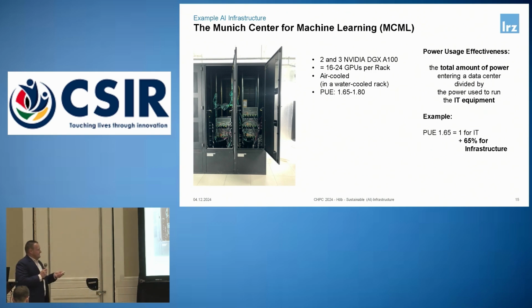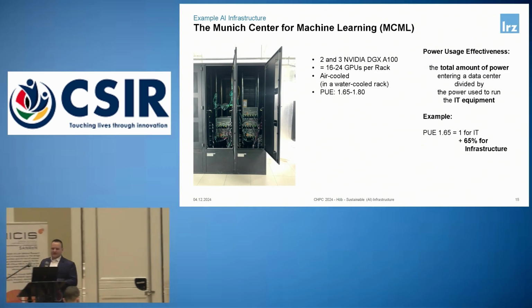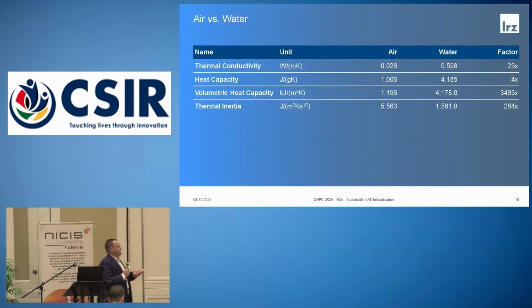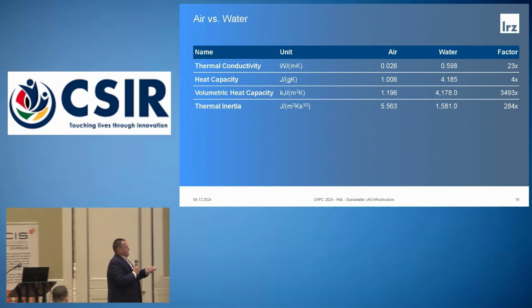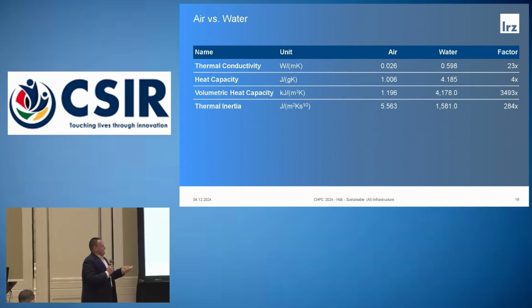Worse, this is the maximum amount we can put in such a rack, because the cooling capacity of this rack is 18 kilowatts, and each of them has 6 kilowatts, so there is a lot of empty space we cannot use for anything else, because all the cooling power is used by those 3 systems. We said, this is not good. We want to have another solution. And we know the numbers. If we use water instead of air, the numbers are much, much better, a factor of 3,400.